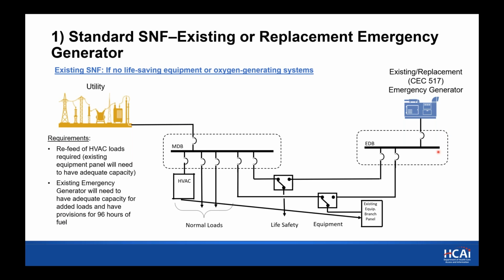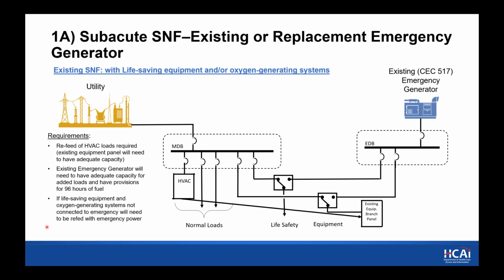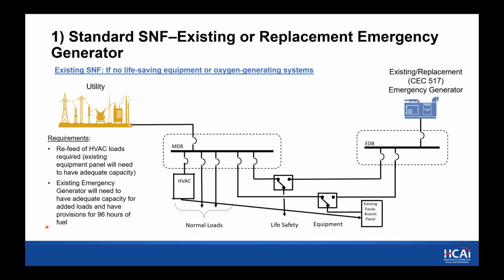One of those transfer switches feeds the equipment branch. So in this case, if it's determined that you need additional HVAC on emergency to satisfy the cooling requirements, you just transfer the feeds from the normal distribution board to the existing equipment distribution board. That would mean transferring the feeds for some of your cooling equipment, and as long as the equipment has the capacity, you could do this. The existing generator will need to have adequate capacity to support this additional load, and we'll need to have provisions for 96 hours of fuel. So we're thinking this is the simplest solution for those facilities that have adequate capacity on the generator.